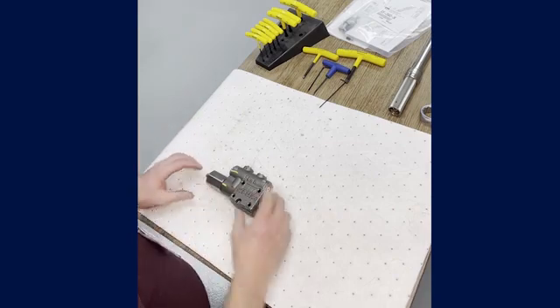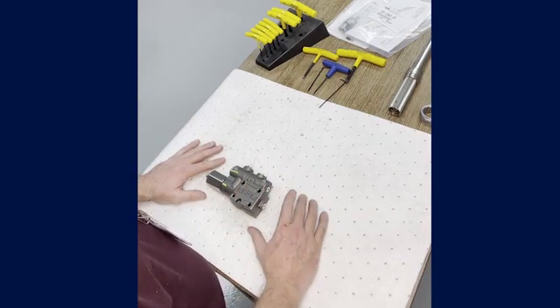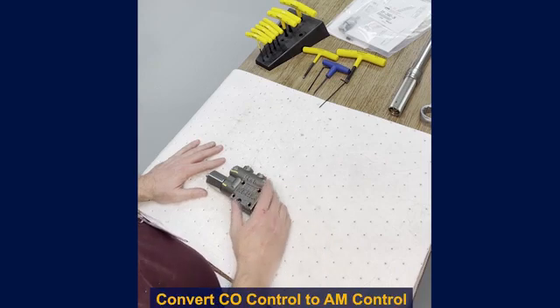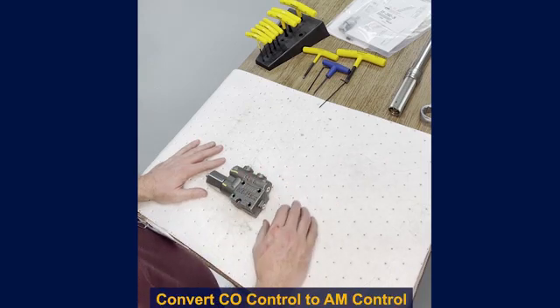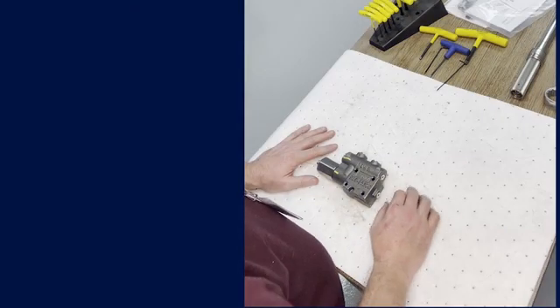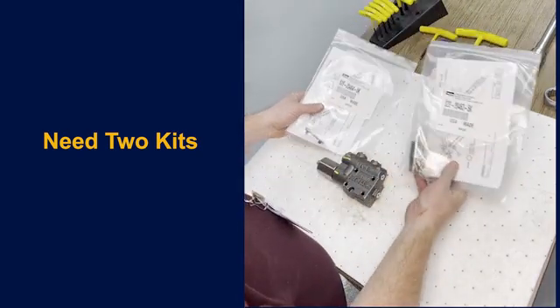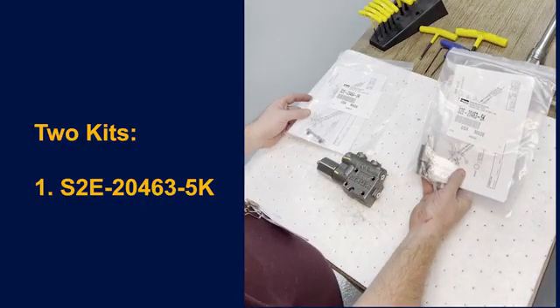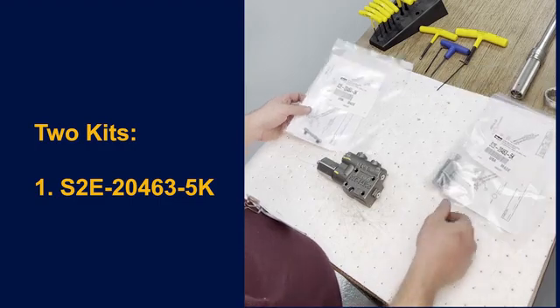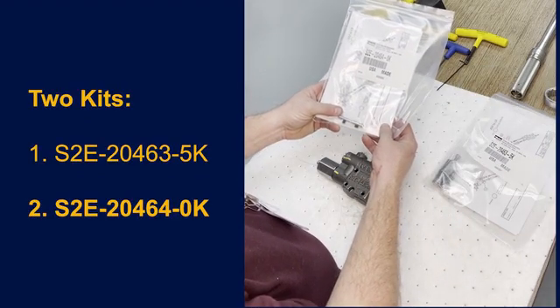I'm going to be showing you how to take a basic CO control — the pressure compensated control — and convert that into the A-M control, which is the remote pressure compensated control. To do that you're going to need two kits.